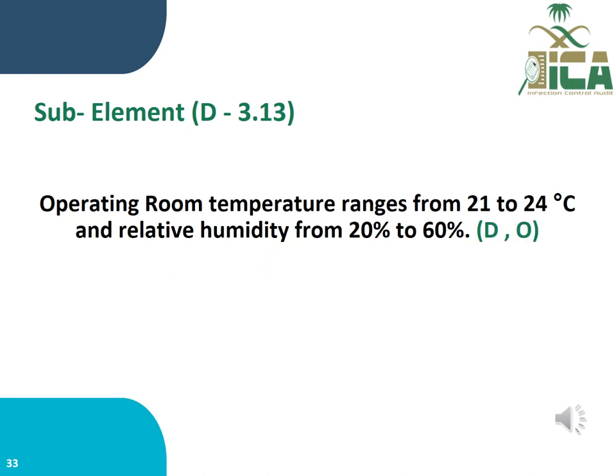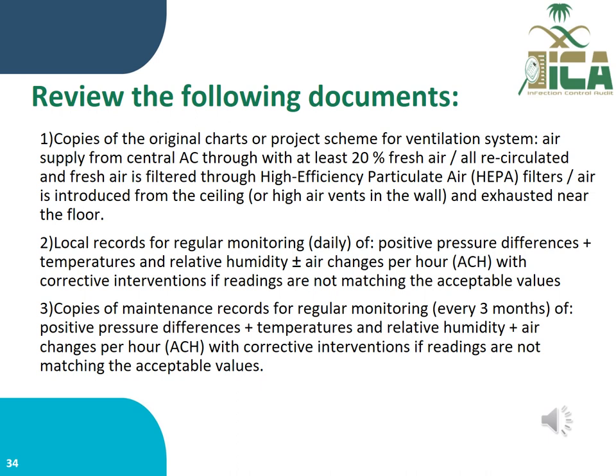Sub-element D3.13: Operating room temperature ranges from 21 to 24°C and relative humidity from 20% to 60%, done by documentation and observation. Review the following documents: (1) copies of the original ventilation system project charts — air supply from central AC with at least 20% fresh air, recirculated and filtered through HEPA filters; air introduced from the ceiling or high wall vents and exhausted near the floor; (2) local records for regular daily monitoring of positive pressure difference, temperature, and relative humidity; (3) air changes per hour (ACH) with corrective intervention if readings are outside acceptable values.